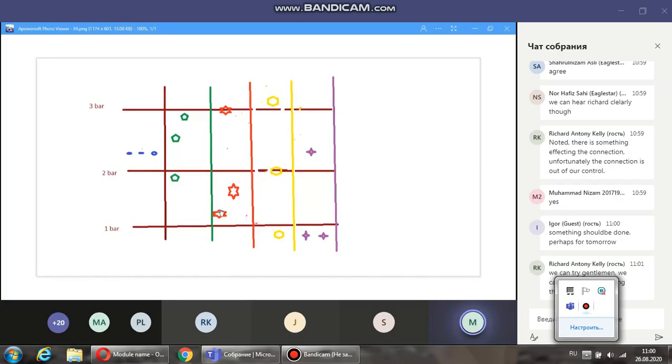Now look at this. This is below 2 bar and this is at 2 bar. So 1.2, 1.6 and 3. So in this case, this will give an alarm saying number 3 sensor is deviating and the average will be only these two, 1.2 plus 1.6 divided by 2. So this will be discarded and you get an alarm.